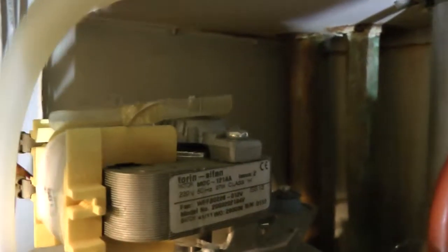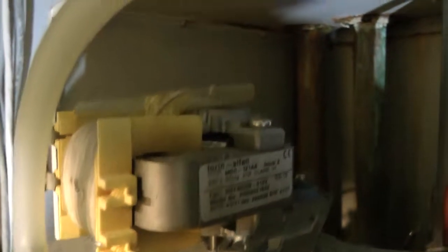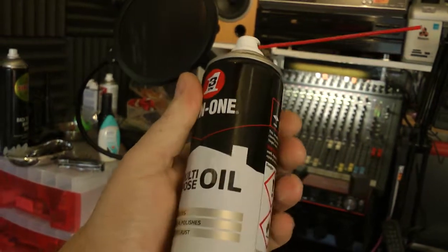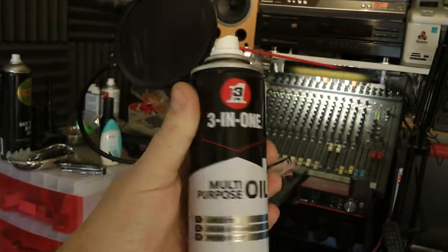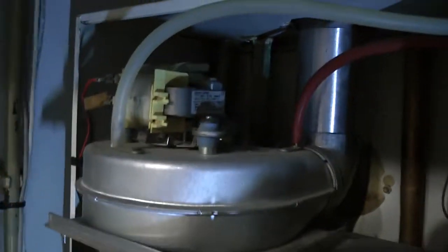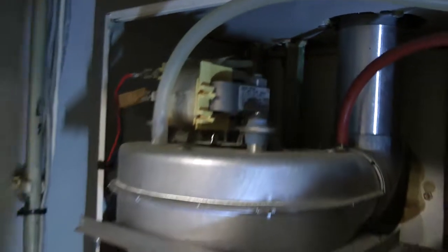I think what's happened, it's just got stiff over the years. So, I'm going to grab some special lube, some 3-in-1 oil in a spray can. I'm going to see if I can get under the armature there, and get some oil onto those bearings before I attempt to start that fan up. So, here we go. I think some of that stuff will do. I just want to hit the top and bottom bearing, just to see if that will help it on its way and tie us over until we get a replacement. What I need to do is get a pair of steps, I think, to get up there and have a closer look at that. So, I'll be right back when I've got some steps.